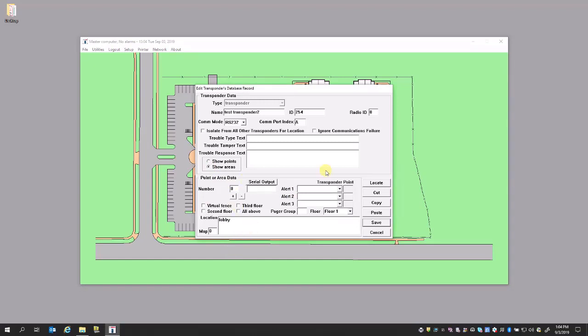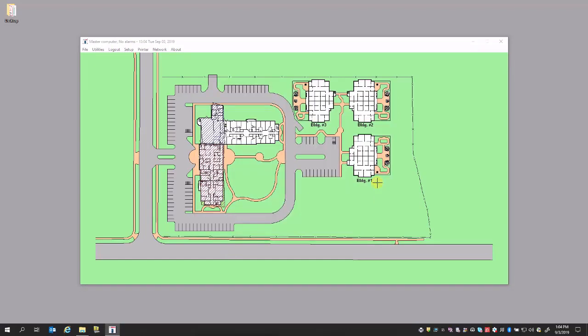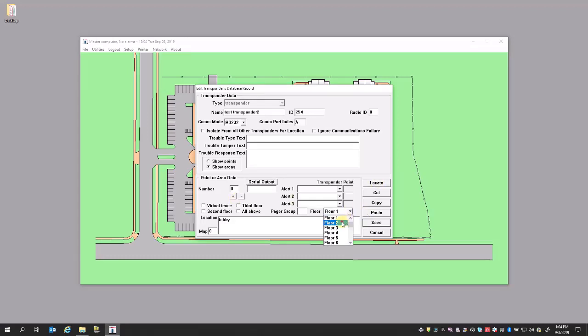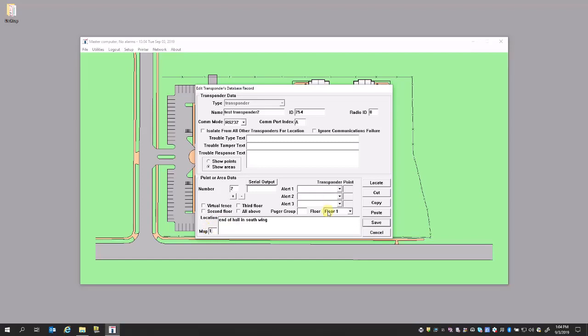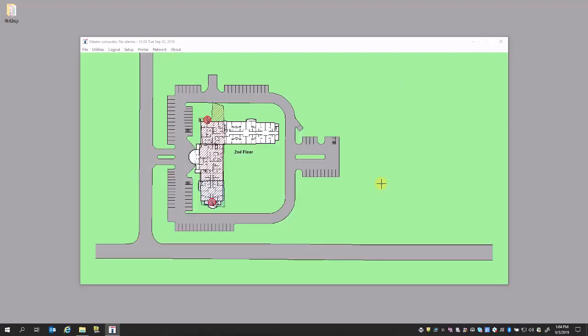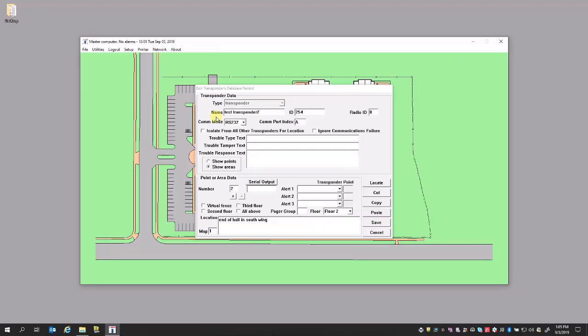The areas all get copied over as well. I need to change the floor number and map number for all three areas. After changing the floor number and map number, if you hit Locate you'll see that the areas are in exactly the same spots on the second floor. The only one we would need to redraw is the top one because that section of the building doesn't exist up there. This is where Copy for the transponder is very helpful in a multi-story facility — it makes installation extremely easy because once you do one floor, you can just copy all your work and change the text.